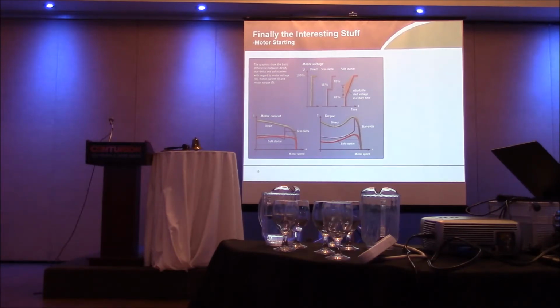This little graphic right here, especially this one in the corner down here, shows what happens to the current going into the motor when you start it. A direct start and an across the line start, where we just close the contacts, that current goes way high. Depending on the style of motor, it will go up to 11 times the full load amps. Now, it doesn't last very long, but it's a big inrush of energy to get that motor turning, to get that fan turning, to get the pump impeller turning, or the escalator moving, or whatever it is. So there's a huge inrush of energy involved when we do an across the line or a direct start.